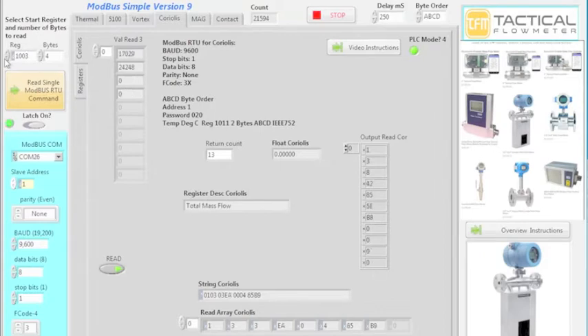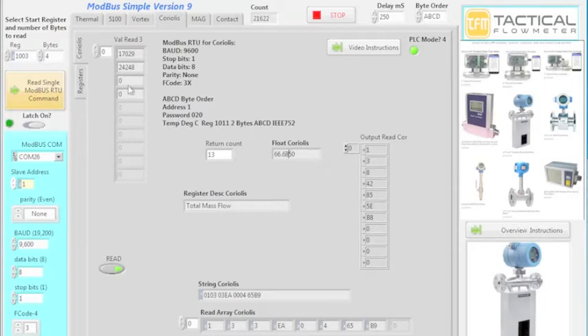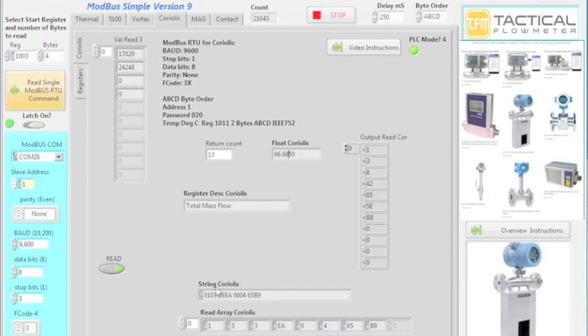These are the variables. The total at 1003 shows 66.69 as the actual number on the display — remember we set two decimal digits. You can set the number of digits you want. You can get Modbus Simple on the website, and this will be for your engineers to work with Modbus RTU. This is a demonstration only, so it's for your enjoyment. Thank you very much — stay tuned.